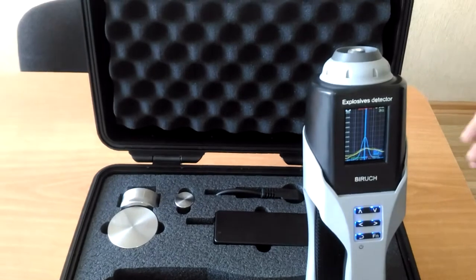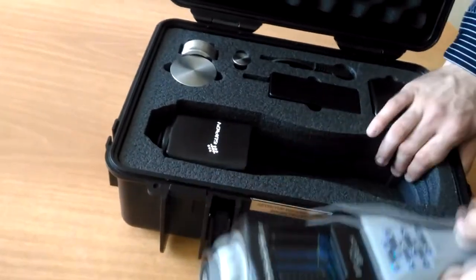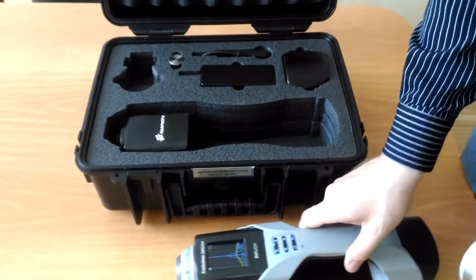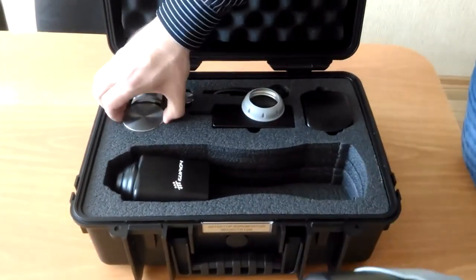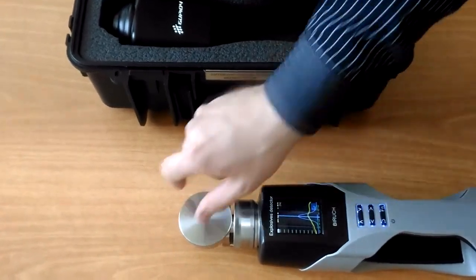When it is needed to use the device under adverse weather conditions — for instance, low temperatures, strong wind, or in smoke or dust premises — it is possible to use remote sampling by taking a probe to the tissue and placing it into the piezo-desorber evaporation chamber. To use it, unscrew the decorative cap and connect the chamber with the vortex system until tight to fix the chamber on the device.